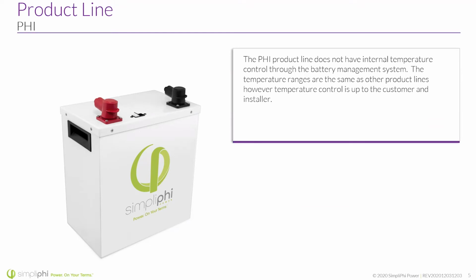It does not sense when it's too low, meaning if you try to charge this battery at 0 degrees Fahrenheit, it will accept a charge and it could cause damage. So this one does not have that kind of built-in intelligence in the battery management system. Not a huge deal for most people if you're in an area where it's not going to be that cold, or if the area where the actual installation is stays pretty warm, it shouldn't be a problem.